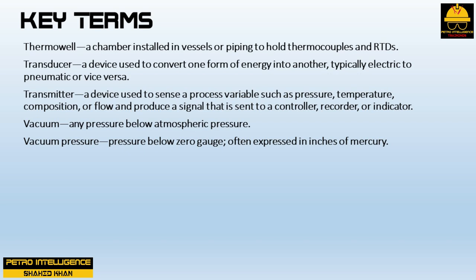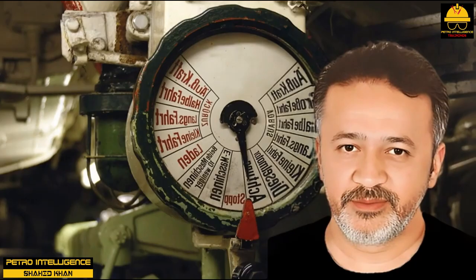A transducer is a device used to convert one form of energy into another, typically electric to pneumatic or vice versa. A transmitter is a device used to sense a process variable such as pressure, temperature, composition, or flow and produce a signal sent to a controller, recorder, or indicator. Vacuum is any pressure below atmospheric pressure; vacuum pressure is often expressed in inches of mercury.